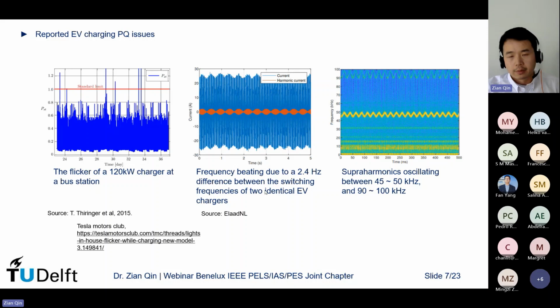The second one shows frequency beating due to two EV chargers of the same model. Having the same model means they have the same switching frequency, but due to accuracy issues, their switching frequency can never be 100% the same. There's a very little difference, which is 2.4 hertz, and this difference in the switching frequency eventually induces frequency beating, which means the total current the two chargers draw from the grid has a 2.4 hertz fluctuation, and eventually induces voltage distortion at the same frequency.